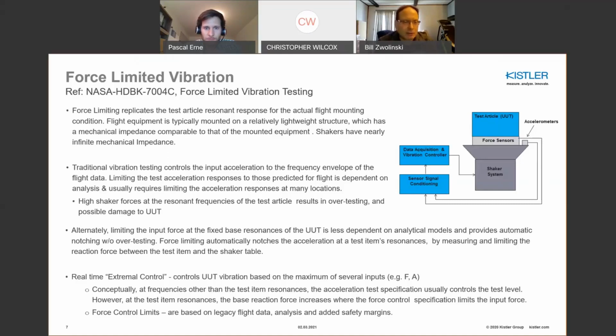So alternately, the limiting of the input force at the fixed base resonances of the unit under test is less dependent on analytical models and provides automatic notching without over-testing. So really the purpose of force limiting is to automatically notch the acceleration at the test item resonances by measuring and limiting the reaction forces between the test item and the shaker table. So, in the control solution, you're really looking at many inputs, and an extremal control solution will basically limit on the basis of the maximum, say, of several inputs entering the control system.